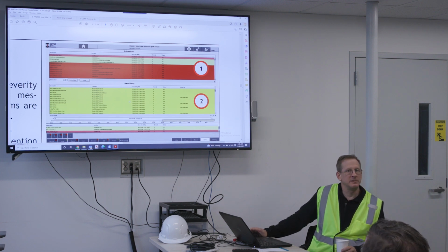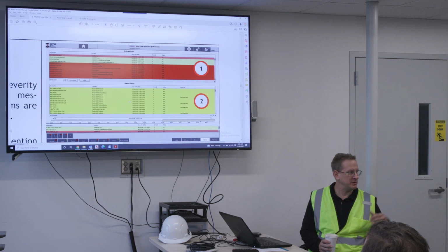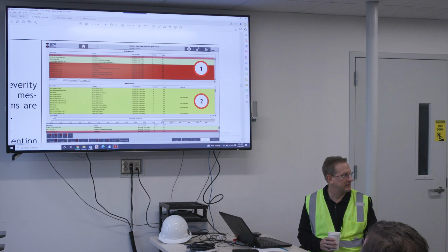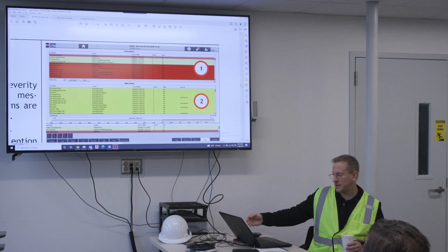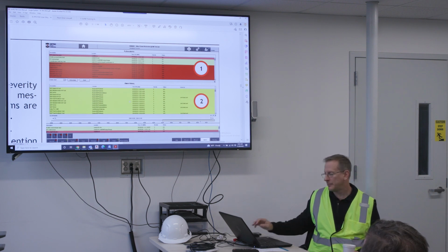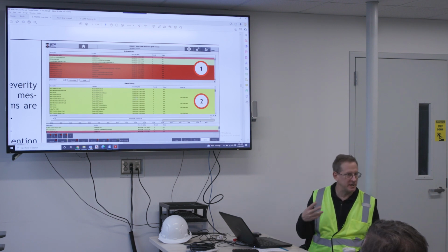So the thing about the HMI is when you have an alarm on your HMI and you clear it, it goes away. Okay, so you're not able to tell any kind of a history record of your alarms. So just kind of like a data logger. Like a data logger, yes. You can actually look into Scada, and not only can you see the active alarms, but you can see alarms that occurred in the past. Yeah.